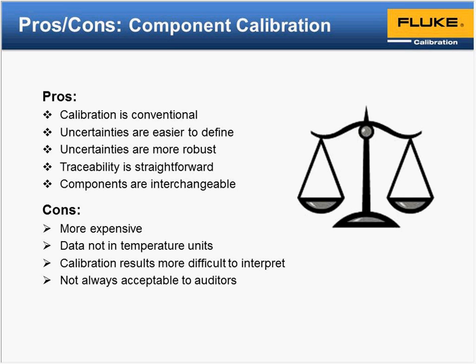Some of the time, on the readout side, you don't get data in temperature. It's usually parts per million, or a voltage, or a resistance, plus or minus. That makes it a little more difficult trying to interpret the results. If you're not familiar with how to take 20 parts per million accuracy and convert it to a temperature, that's something you'd have to talk through with an auditor.